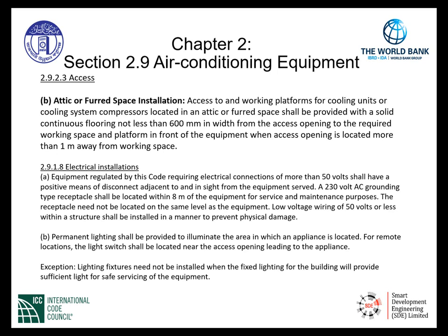2.9.2.3, Item B, Attic or Furred Space Installation. The access to and working platforms for cooling units or cooling system compressors located in an attic or referred space shall be provided with a solid continuous flooring, not less than 600 millimeters in width from the access opening to the required workspace and equipment platform in front of the equipment when the access opening is located more than 1 meter away from the working space.